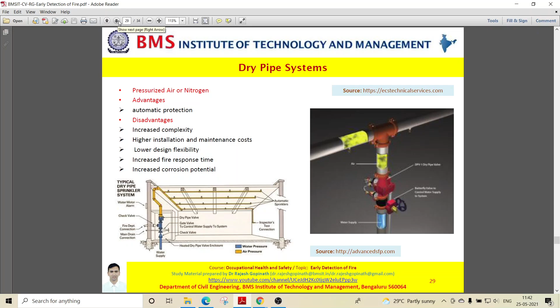But having said this, it also has certain disadvantages. When compared to a wet pipe system, this is much more complex because it's not water flowing in the pipes, it is pressurized air or nitrogen gas. So the system is much more complicated. Automatically, the installation cost is higher and the maintenance cost is higher. In the event of damage and repair, you don't have that much flexibility. Even expansion doesn't happen easily. And yes, there is a greater potential for corrosion. And compared to your wet pipe system, the fire response time is increased.